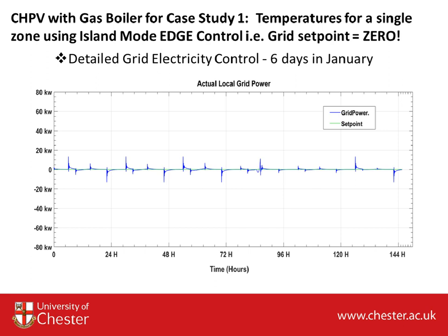Obviously, achieving 0 is impossible because the system of CHP generation has inertia, so does thermal storage, so would battery storage. But you can see here we've got pretty good results, plus or minus 20 kilowatts within typically a 3 megawatt system. That's pretty impressive.